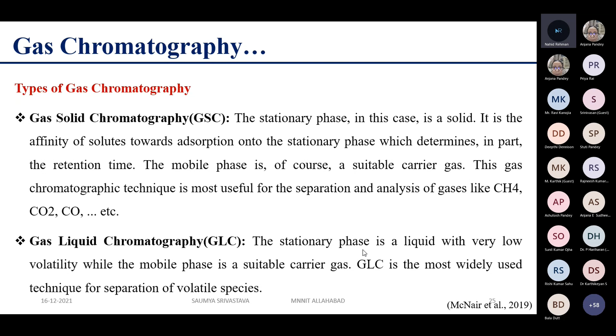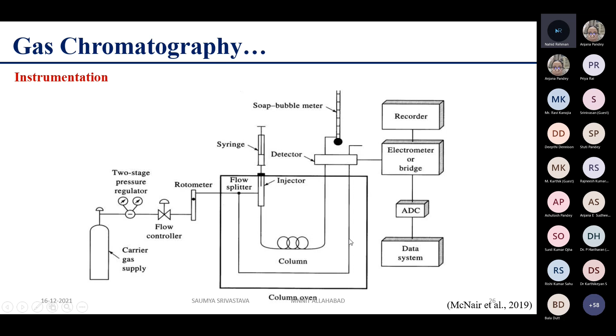This is the instrumentation of gas chromatography. The carrier gas is passed through the flow controller, followed by the rotameter and the sample injector. The sample injector is the place where we inject our sample with the help of a syringe, and it is connected to the column where the separation of solutes takes place, followed by its connection with the detector, which records the data related to incoming solutes and then sends data to the recorder or the computer system.